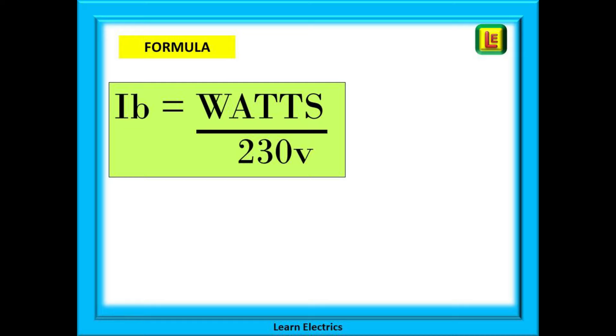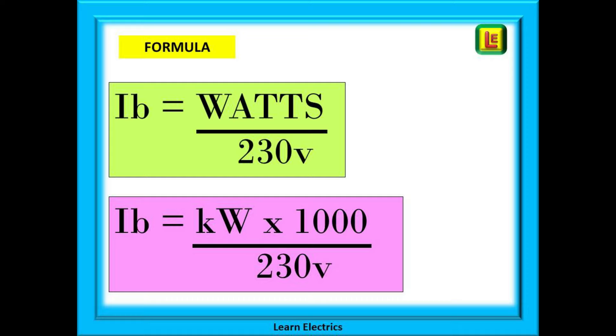The formula to use is very simple. Take the appliance rating in watts and divide it by 230 volts to give us the design current or IB. 230 volts is the nominal voltage rating for the UK — and yes, it is actually 240 volts when we measure it, but we use 230 volts for all our calculations. If the appliance rating is shown as kilowatts or kW, this just means thousands of watts. Take the kW figure and multiply it by 1000 before dividing it by 230 volts.